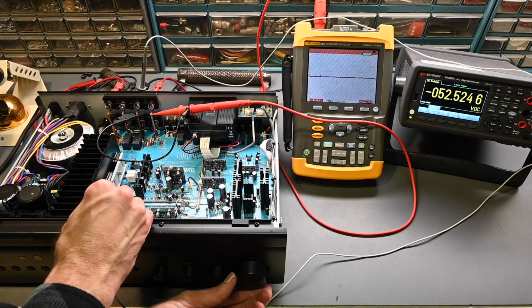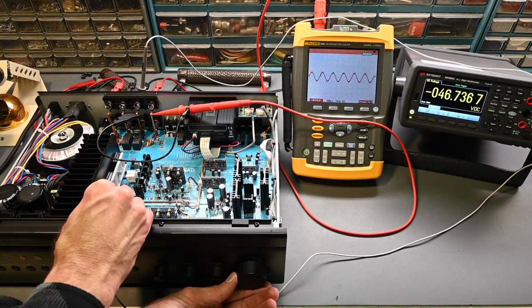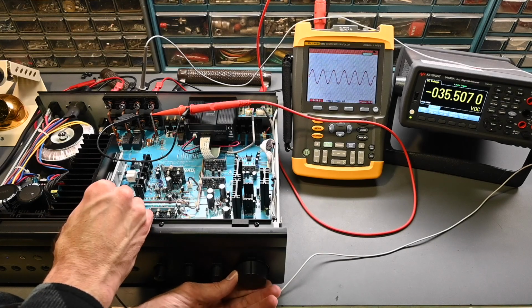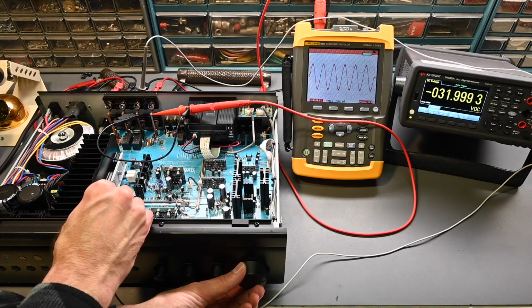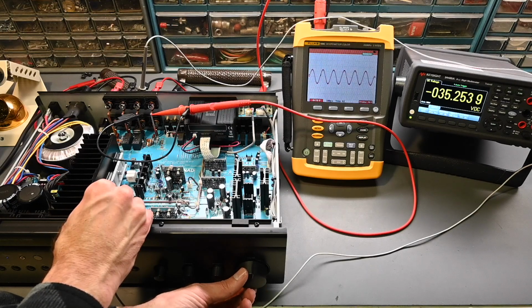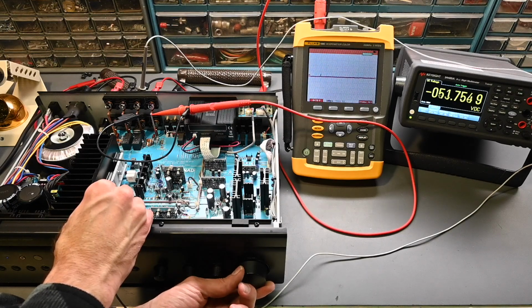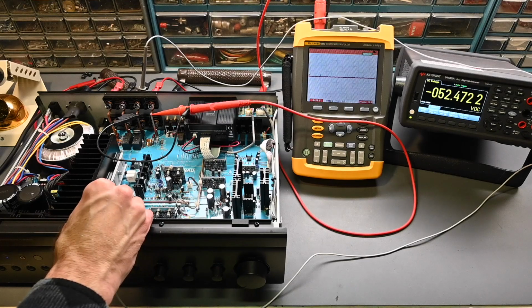I'll do that again. Turn this up. 47, 46, and then 37. If I keep increasing this, we go all the way up and drive this all the way up to about the clipping point right there, and it pulls it down to about 30 or 31 volts, which is perfectly normal. But you can see there's about a 10 volt drop that suddenly occurs.